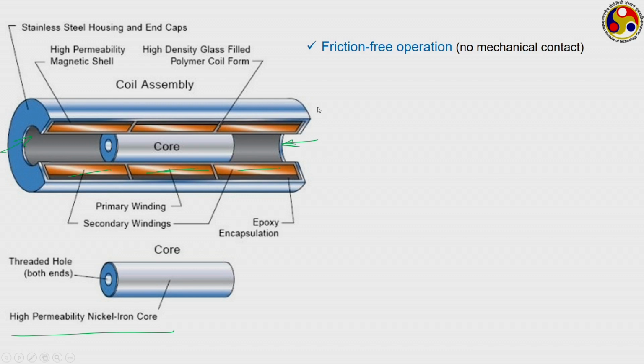It offers huge advantages compared to other displacement measuring devices. The first big advantage is friction-free operation. There is no direct mechanical contact between different components. The primary winding, the secondary winding, and the core are all separated from each other, and therefore can move without any rubbing effect.